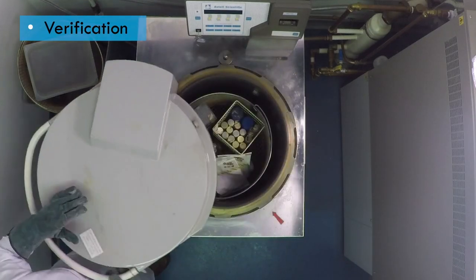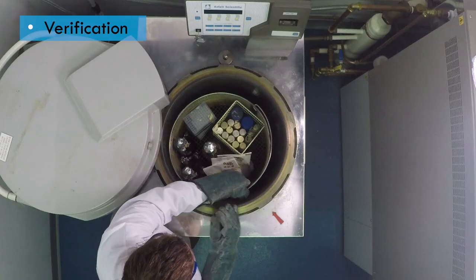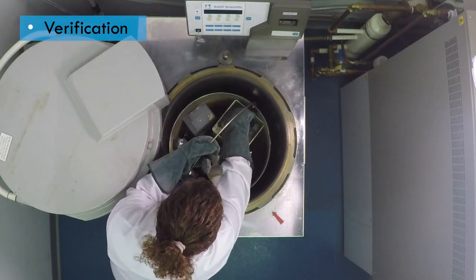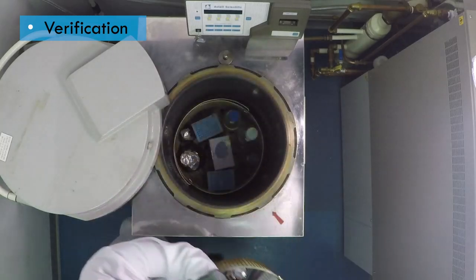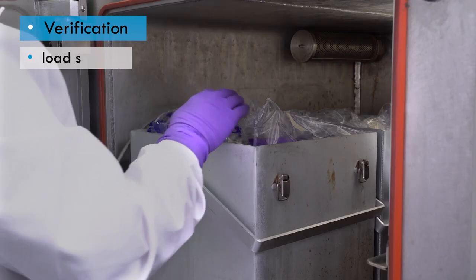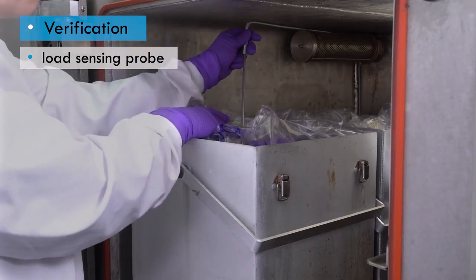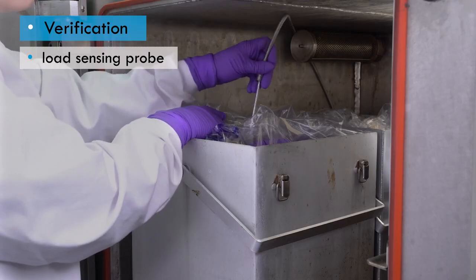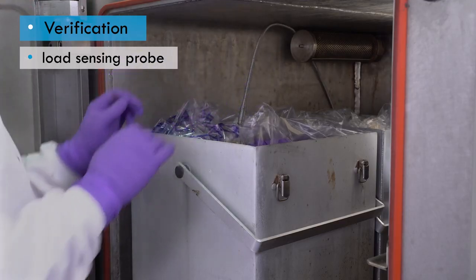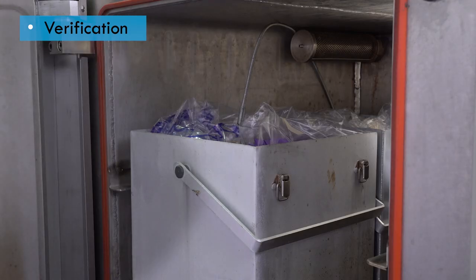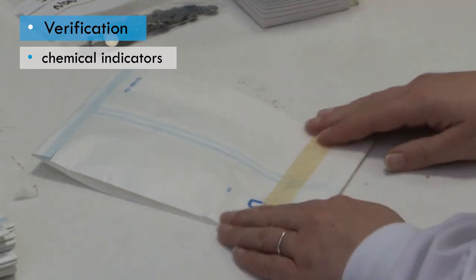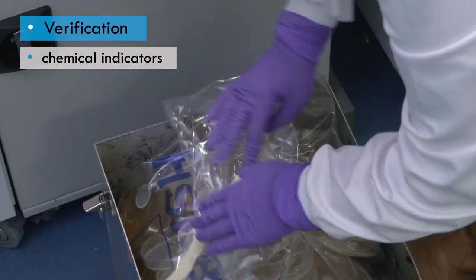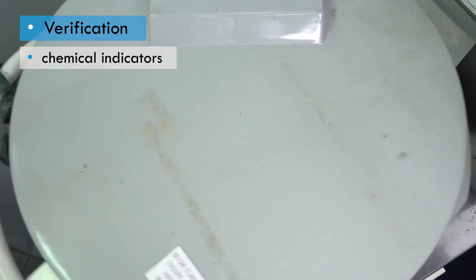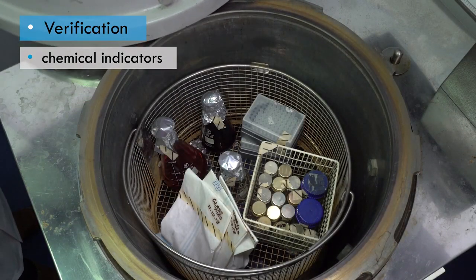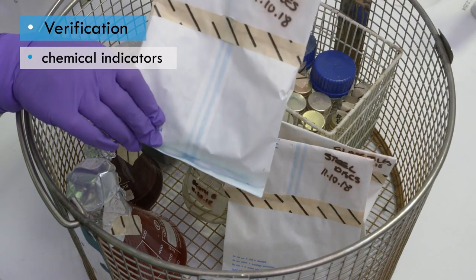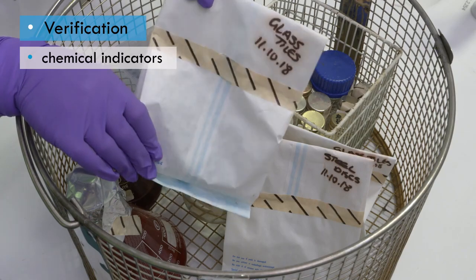The autoclave cycle should be verified before first use and periodically thereafter to make sure the cycle parameters are effectively killing the microorganisms handled in your laboratory. Some autoclaves can be fitted with load-sensing probes, which can be inserted into the center of a dense load to monitor temperature and verify that sterilization temperature has been achieved. Chemical indicators, such as autoclave tape, use heat-sensitive ink that changes color when it reaches a set temperature. This is a useful indicator, but it's only checking the temperatures on the outside surfaces, not the contents, and it doesn't tell you if the required pressure and dwell time were achieved.